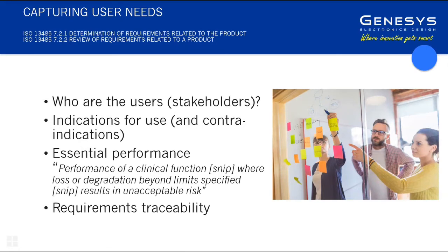The easiest way to do this is with a structured sequence of codes, where each user need gets assigned a code, and then verification and validation of parameters against that user need are identified by that code, so that you can provide the traceability. You can do the traceability with a large Excel spreadsheet. There are third-party systems. For example, one's called Doors, which I believe is incredibly complicated to use. It's Green Light Guru as well. Green Light Guru doesn't really have a formal traceability facility that's all that effective, but you can use it. For the devices we use an Excel spreadsheet plus numerical codes that are cross-referenced through the documents.